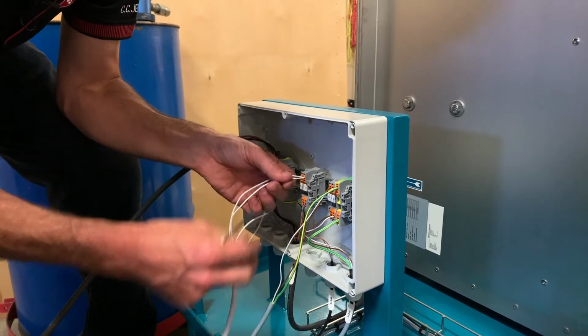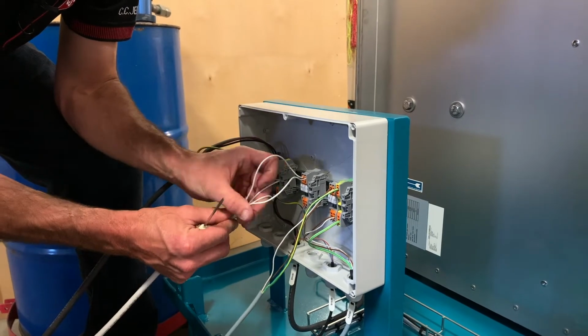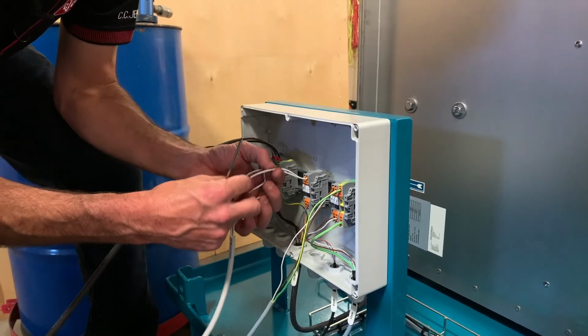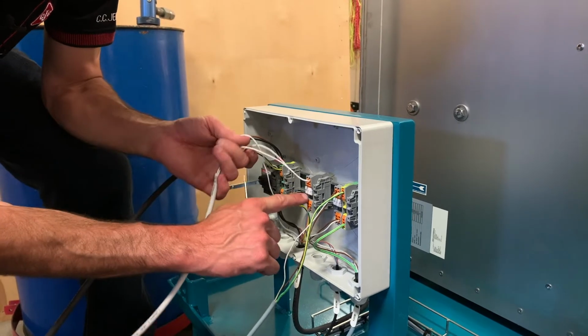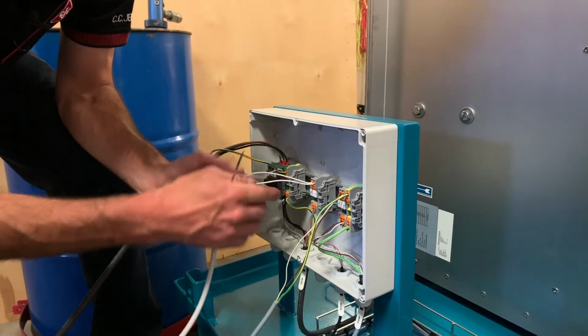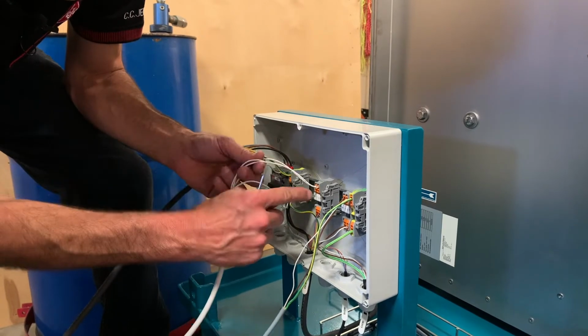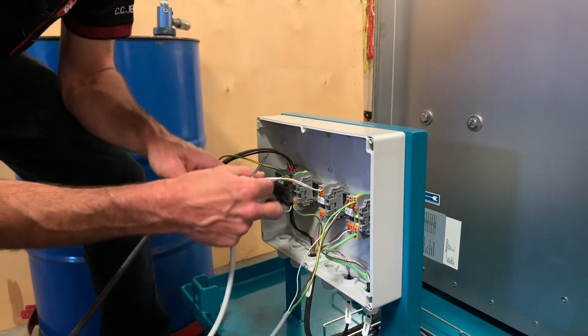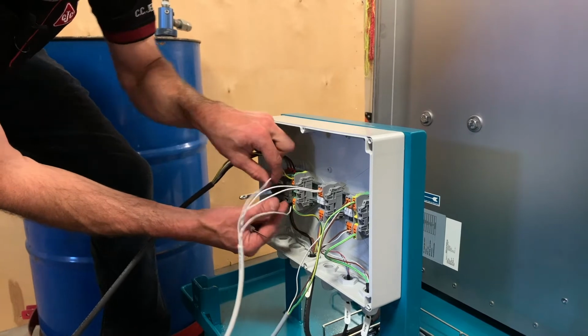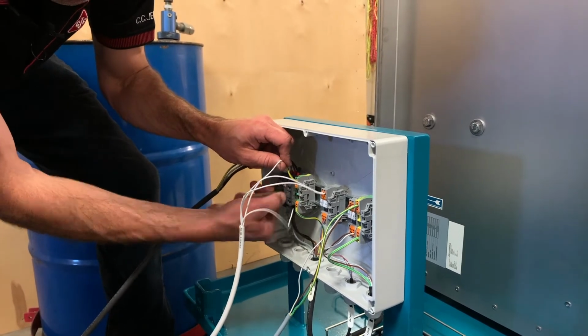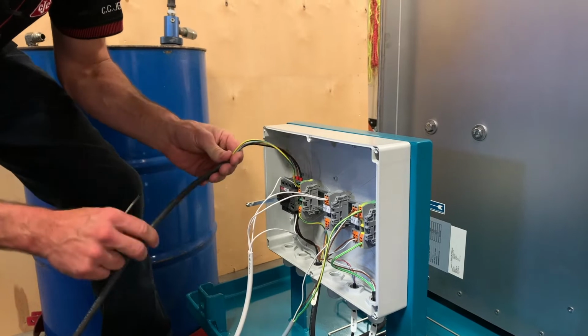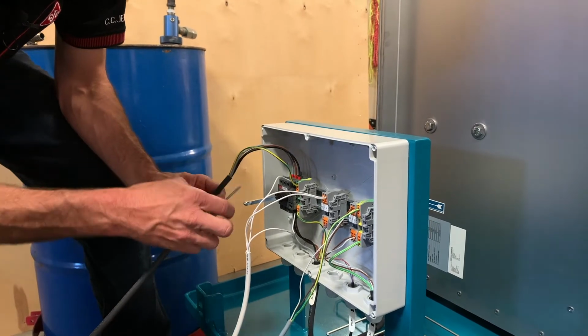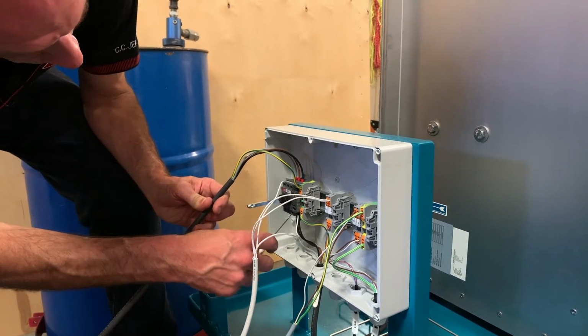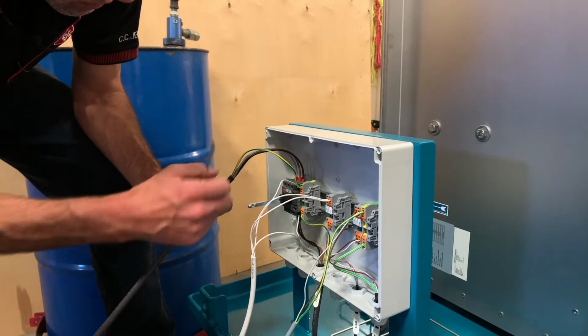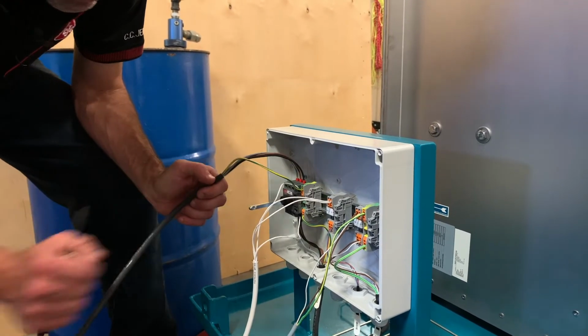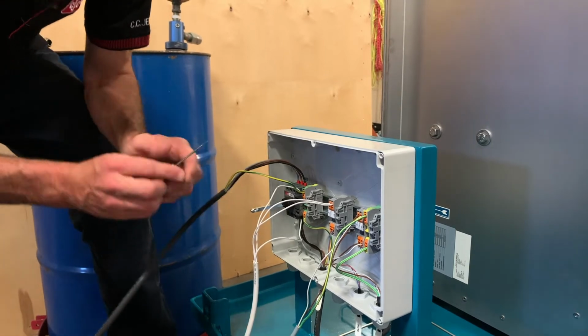You'll see the next wire with the 4 individual wires are numbered, and those correspond with the terminal numbers on the terminal blocks. So connect 1 and 2 to this middle block, and 3 and 4 go to the auxiliary leads on either side of this disconnect switch. And then you have the main power leads coming in here, and that just, again, corresponds to the colors below, line 1, 2, and 3 for the power plus the ground, and that has your electrical connections covered.